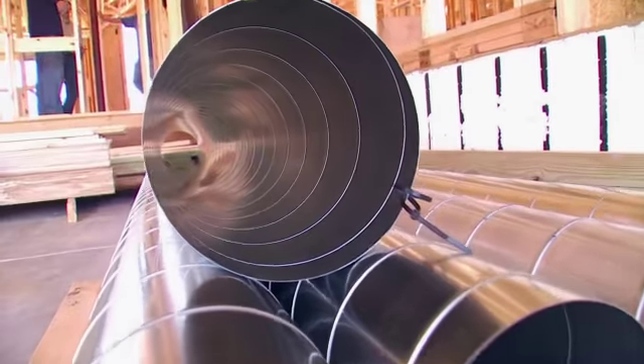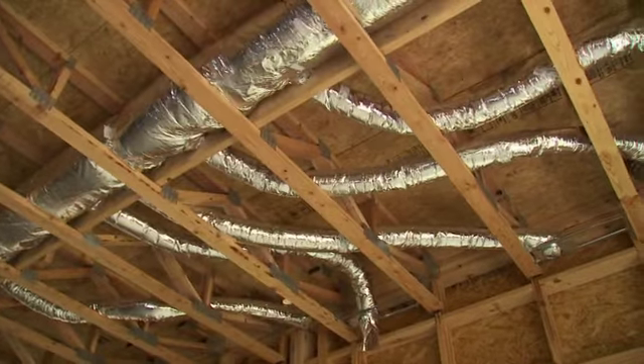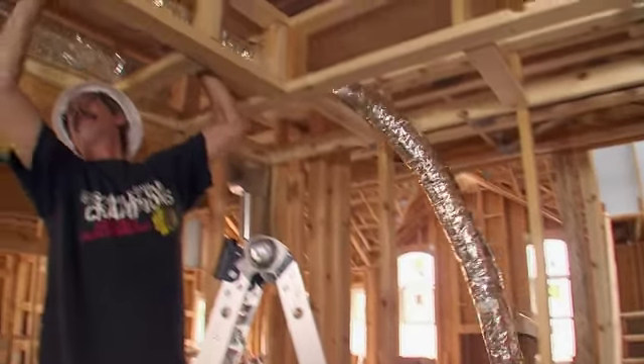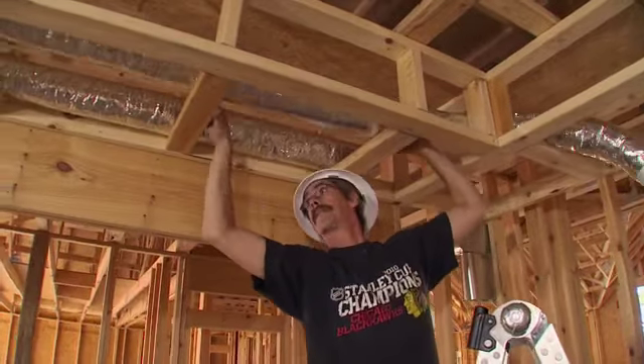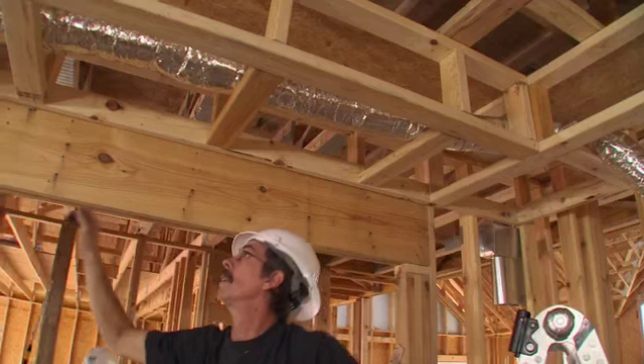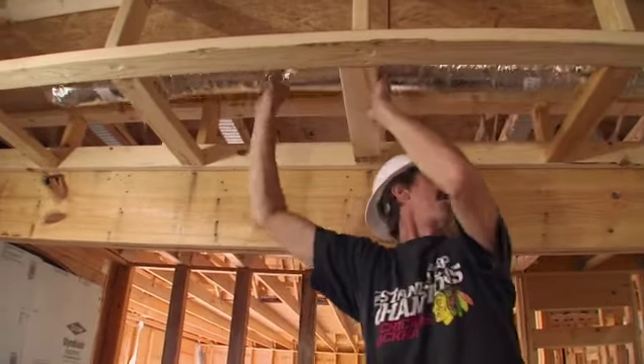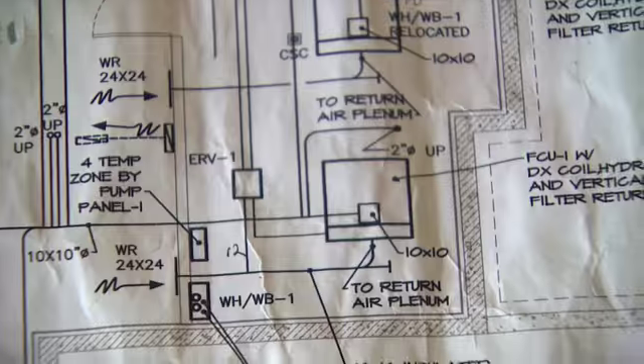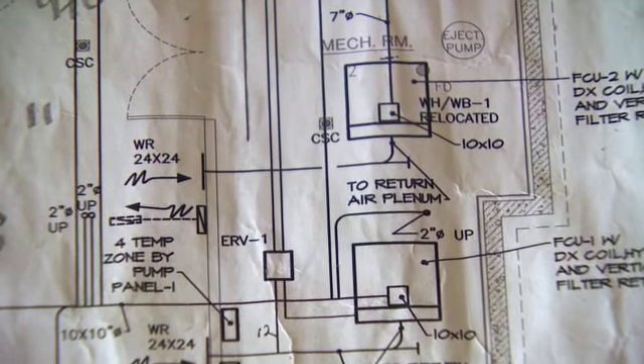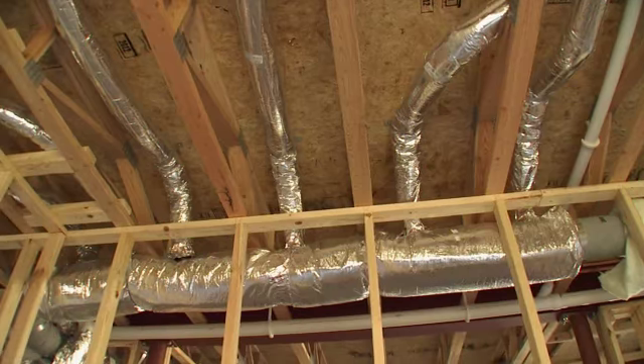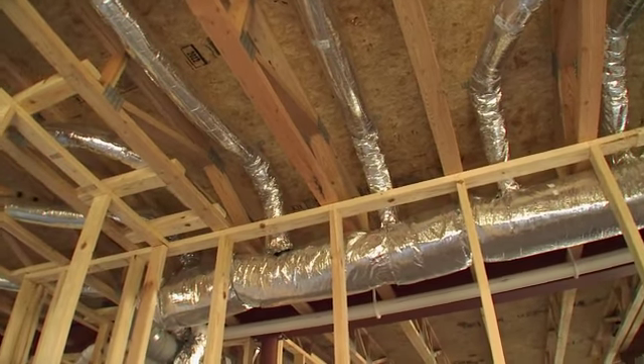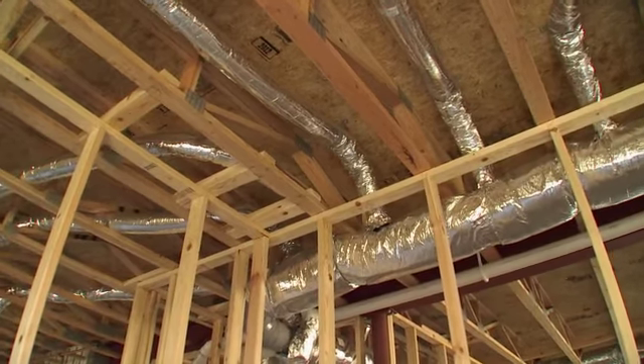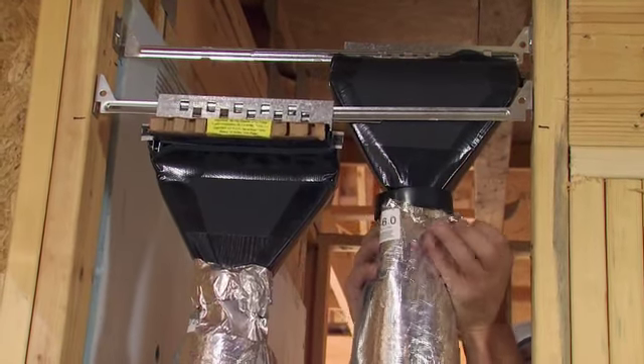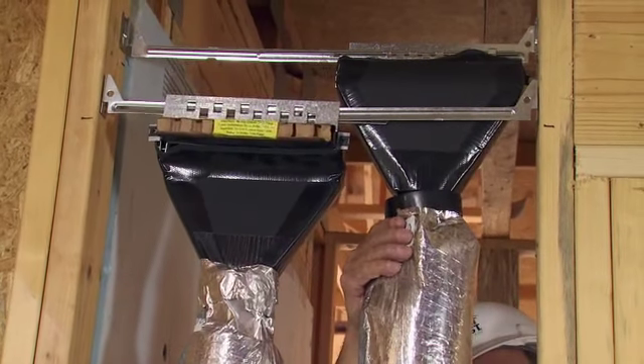Product we're going to use for the heating and cooling in this particular application is a small duct, high velocity, central heating and cooling system. And in this particular application, we chose it because of the very limited thermal transfer between inside and out, we don't need the big ductwork in here. We want as much built space as we can possibly get in this home. With the system we're installing, the main plenum, instead of being 8 inches by 30, it's only 7 inches round. Coming off of that are very small 2-inch ducts, which terminate into very linear diffusers, which are about yay big. So the impact on the home is very small.